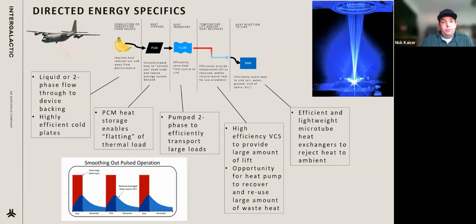The next piece, and the phase change material thermal battery is key for this, is that there's a very high intensity load that's relatively short duration. To size a thermal management system that holds that peak load all the time would be massive. Using a phase change material thermal battery to absorb that load and let the rest of the system run at some lower steady state all the time really helps size down the whole thing. So that's key—you can see in the diagram, those red bars are the pulses, and the average load is the blue line. It levels the whole thing out, and you can really downsize the system by quite a bit.